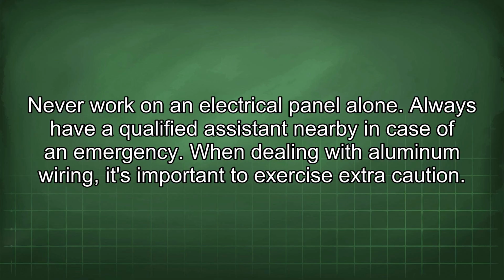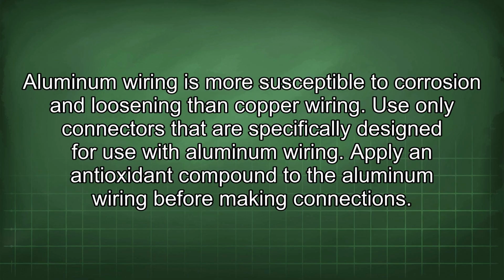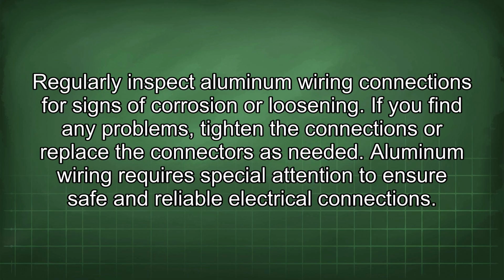When dealing with aluminum wiring, it's important to exercise extra caution. Aluminum wiring is more susceptible to corrosion and loosening than copper wiring. Use only connectors that are specifically designed for use with aluminum wiring. Apply an antioxidant compound to the aluminum wiring before making connections. Regularly inspect aluminum wiring connections for signs of corrosion or loosening. If you find any problems, tighten the connections or replace the connectors as needed. Aluminum wiring requires special attention to ensure safe and reliable electrical connections.